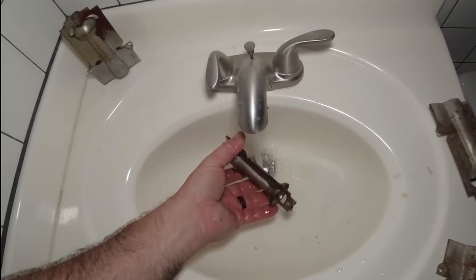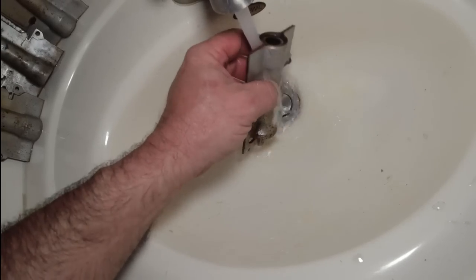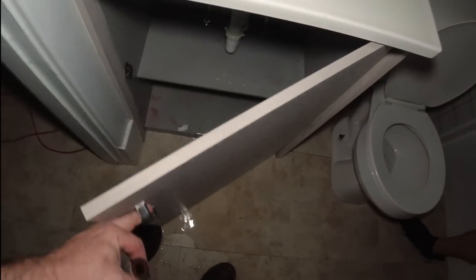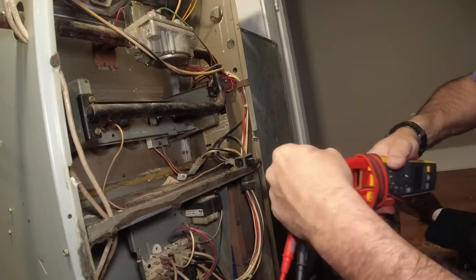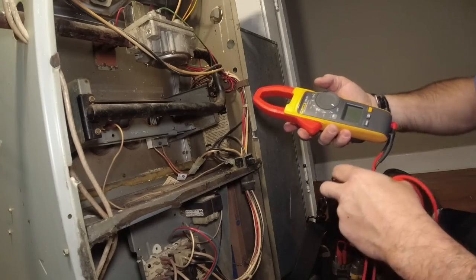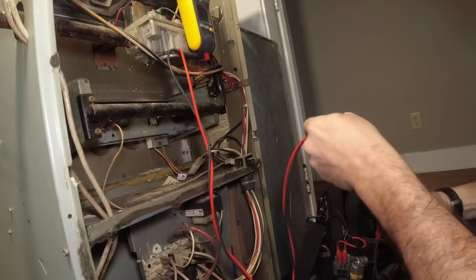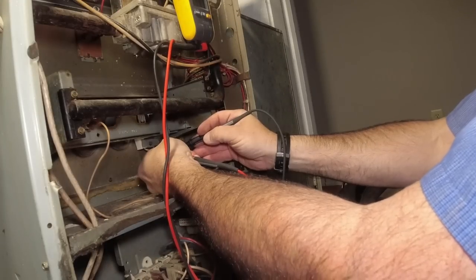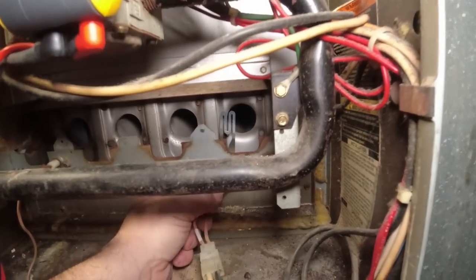We might be able to spit-shine this thing up and make it at least more honorable. There's a bunch of water coming out. The drain must be plugged up. Let's check this igniter — just about to tell you it's probably bad or going bad. For Carrier they usually want it under 95 ohms. This one reads 73 ohms, so believe it or not, it's actually still pretty good — definitely closer than I care for.